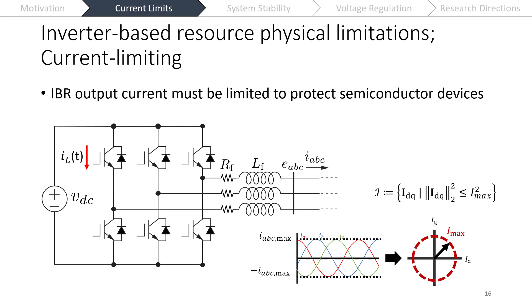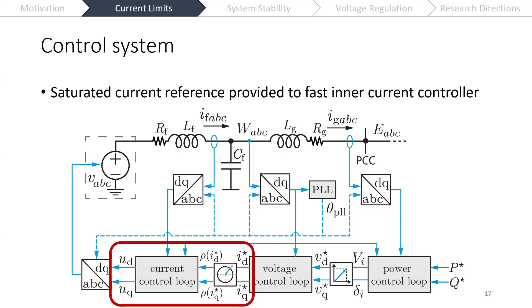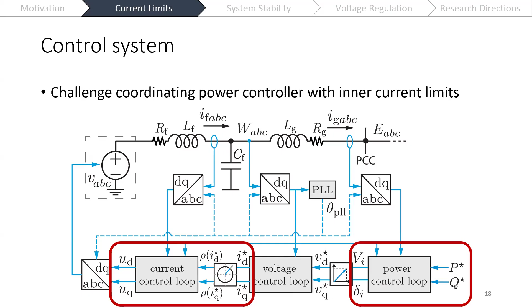So whatever the provided ID and IQ reference values are, we just saturate them to be within that current magnitude limit. And then, assuming this inner current control loop acts fast enough, our currents won't go beyond that value. However, we have a challenge that comes up with this nested control loop structure, where we need to coordinate our outer power control loop with these inner current control loops, given that our power control loop might be requesting references that we might not be able to achieve, which can destabilize our system.